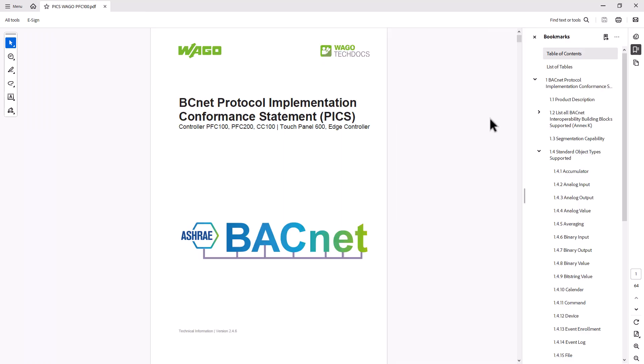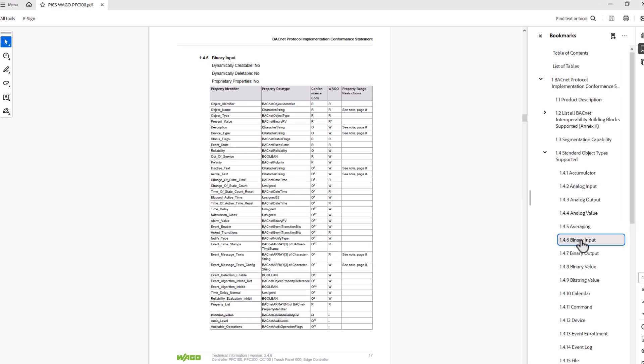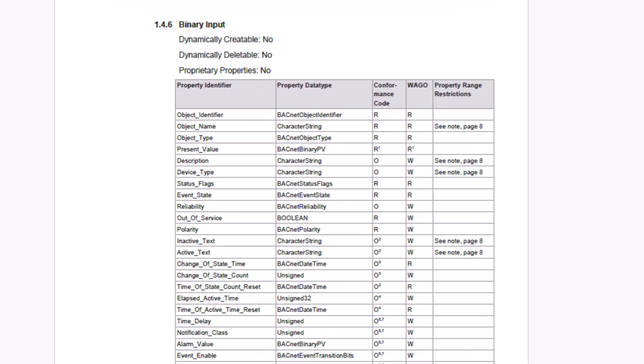Here is the PICS table for the controller we use in this video. Let's scroll to the binary input object to the list of all input properties. The most interesting property for this video is the present value, which indicates the current state of the input, either true or false. Here we see that we can only read the present value, which is functionally correct for an input.